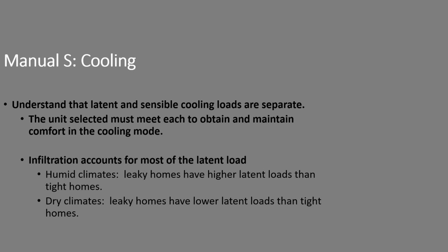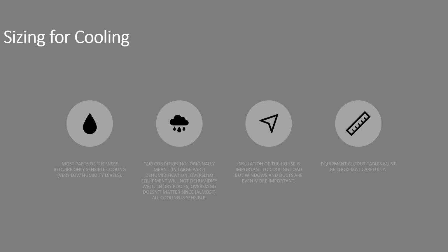Manual S, when it comes to selecting these things, understand that latent and sensible cooling loads are two separate items, and you have to meet each to obtain comfort. In cooling mode, the good news is our latent load is really tiny. Just to show you how this works, infiltration accounts for most of the latent loads. In humid climates, leaky homes let that moisture in. In dry climates, it's so dry outside that the leaky homes tend to have lower latent loads. Sizing for cooling, in most parts of the West, it's easy to handle the dehumidification. Air conditioning originally meant two things, dehumidification and lowering the sensible temperature.